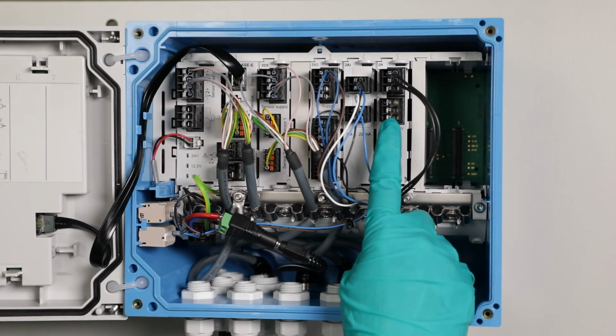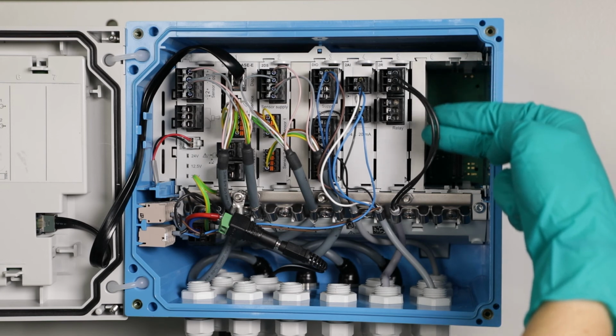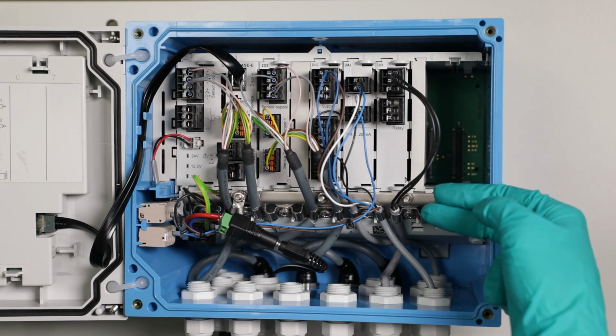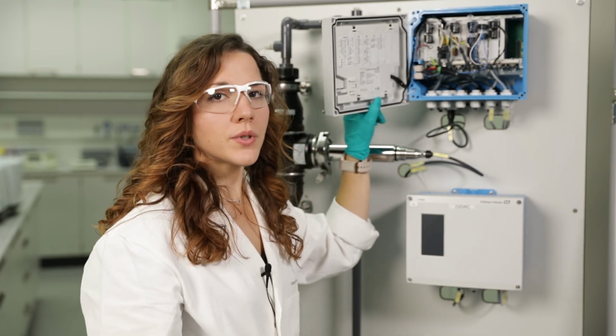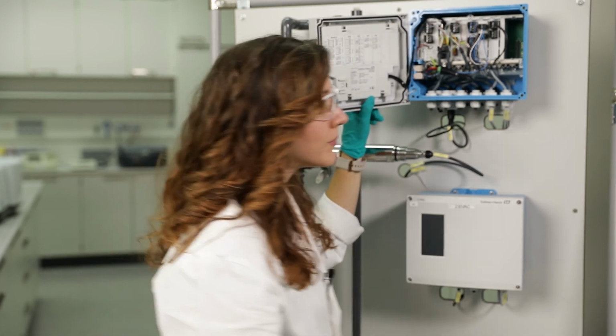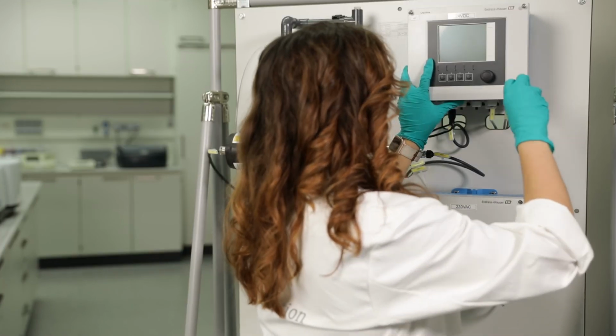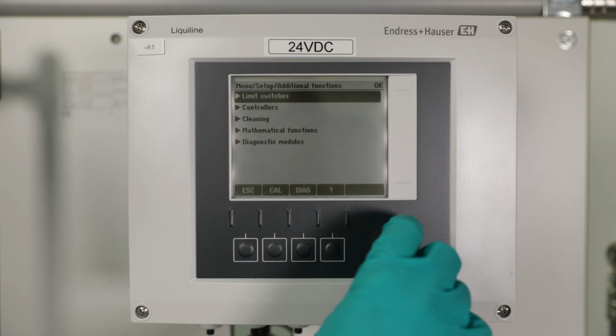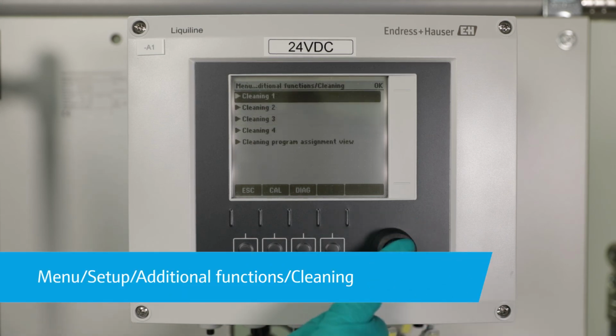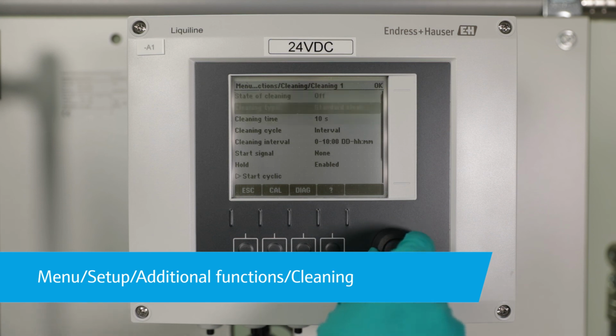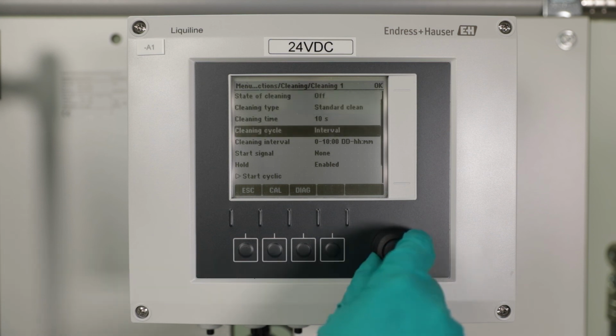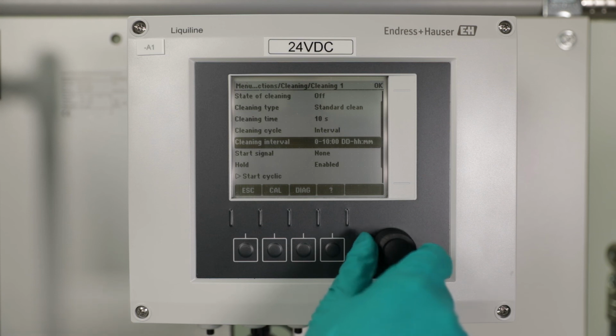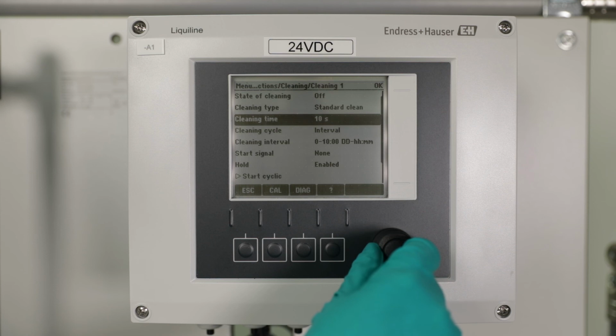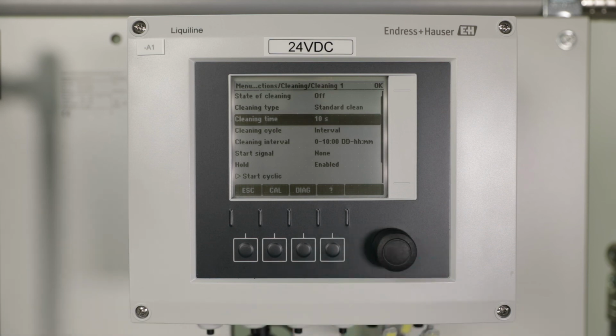Your Liquiline device just needs a free relay at which the pneumatic control valve or the CYR52 generator can be connected. Use only terminals of an additional module in the Liquiline. Do not use the alarm relay of the base module. The Liquiline offers the possibility to define a cleaning program and to determine the cleaning intervals and times according to your needs. If no empirical values are available, we recommend starting with an interval of 10 minutes and a time of 10 seconds for compressed air cleaning and adjusting if necessary.